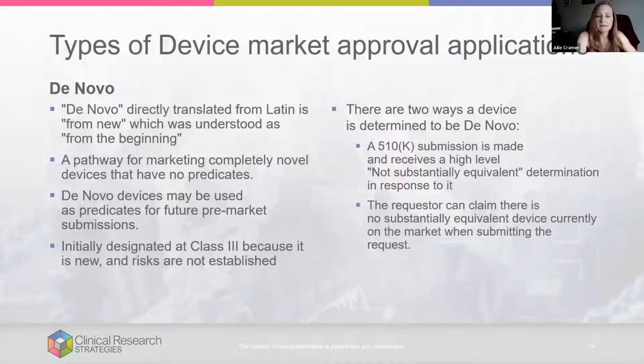One is your 510K submission with a predicate has been determined to be not substantially equivalent. So you think it's equivalent, you put your whole submission around this one predicate, and the FDA says, no, not substantially equivalent. So sorry, you're going to have to be pushed to de novo. So that's one. Or two, you can go into a de novo saying, I request, there's no substantially equivalent device out there. So I'm going to request going into it proactively a de novo application.